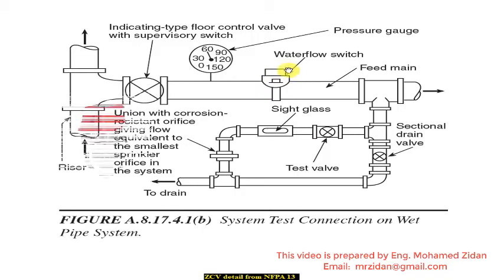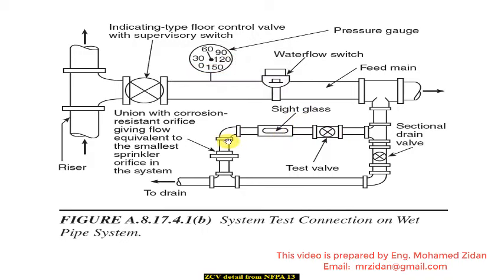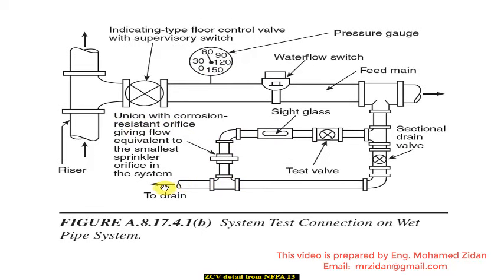Then we will have a flow switch. After that we will have a T-connection for draining the line in case of cleaning or flushing. The drain line will be controlled by a gate valve, and we also have a bypass on this line which includes a test valve or sight glass to check the quality and flow of the water. After that we have an orifice. At the end point of the drain line, we can connect a hose to the nearest floor drain or connect to the nearest drain line.